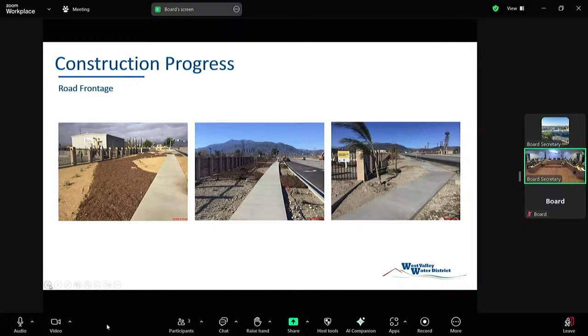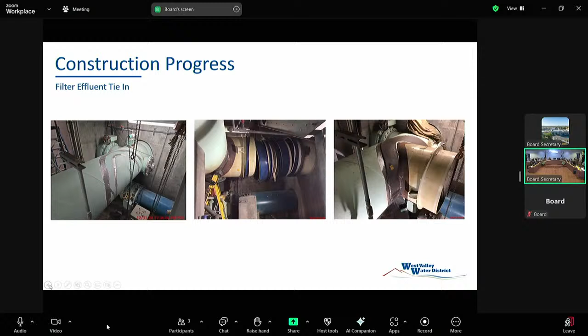This was a very unique shutdown that had to take place. I wanted to share this with the board to talk about the complexities of working in a live treatment plant. This was the filter effluent pipeline going to the UV disinfection system, and there's just not a lot of space down here—there's a cement ledge walkway right above, and just past this it goes into the UV station. Typically when you want to install a tee, you'd cut the pipe, weld on some flanges, and put a tee in. But there wasn't enough space to do that here, so the contractor came up with a creative solution: a metal saddle welded onto the pipe in place. It required a shutdown of the entire plant. They put the saddle over the top, with a welder on the outside and another who climbed inside the pipe to weld the whole thing together, then painted and coated it for corrosion protection. This is just one example of how hard it can be to work inside a treatment plant.